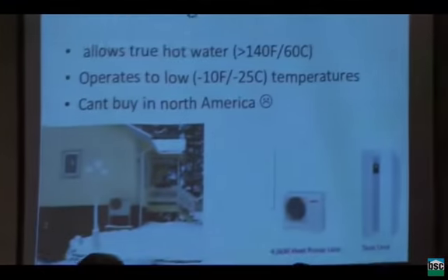Now, I'm going to get wackier yet before I get to CO2, before I get to ground source. Switch to CO2 as a refrigerant, and now we're like, very cool things can happen, or hot things, depending what you'd like. So it's easy to make hot water at temperatures over 140 degrees. The pressure required to do that is somewhere like double the R410 pressure. So if anyone plays around with air conditioning units and you see the pressure in your 410 rise to 600 psi, usually you'll get very worried. That would be kind of like normal operating pressure for CO2. And when you're trying to get to temperatures of hot water of 140, 145 degrees, 900 to 1,000 psi would be normal, which means that you've got to have good seals and thick walls in your pipes and all that stuff. It also works rather well at temperatures down well below -10.